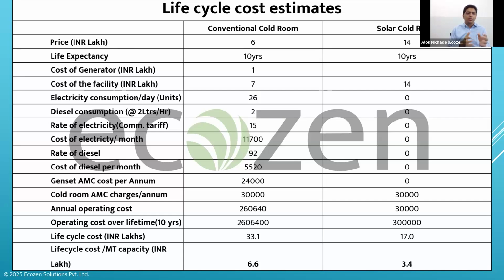If we compare conventional cold rooms to solar cold rooms, the initial investment required is on the higher side for solar. But if we talk about uncertainty, even a 1 hour power cut in a location will lead to changes in temperature. And even if you put a diesel generator there, it will drastically increase the monetary expense required to ensure continuous service to these perishables.